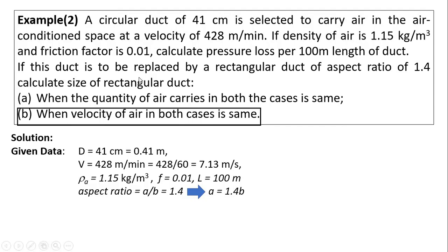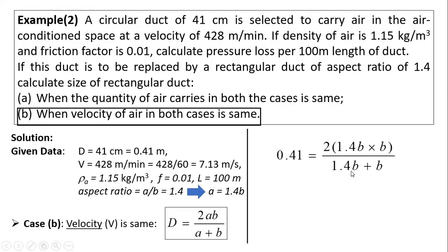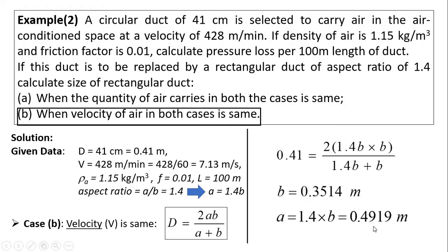For the second criteria — replacing the circular duct with a rectangular duct of aspect ratio 1.4 when velocity is the same — we use the formula D = 2ab/(a + b). Substituting a = 1.4b and the known value of D, and solving, we get b = 0.3514 m and a = 1.4b = 0.4919 m. So in this way we can calculate equivalent dimensions of rectangular duct for a given circular duct. Thank you.